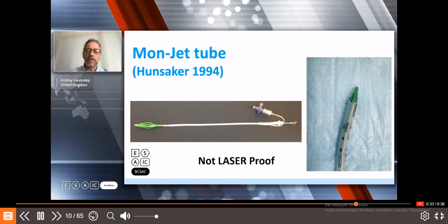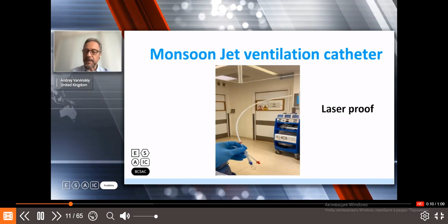Now, there is a Monsoon jet ventilation catheter that appeared later on in conjunction with a Monsoon jet ventilator. That is a laser-proof tube, and let's have a look at it. It has the opening for the CO2 and airway pressure measurement. It has a stylet to put it in. It has a laser-resistant Teflon coating. So this tube you can use for any operation involving laser. And there is a Luer lock connection with a lumen for the CO2 and airway measurement. So that is the major advantage of this tube.